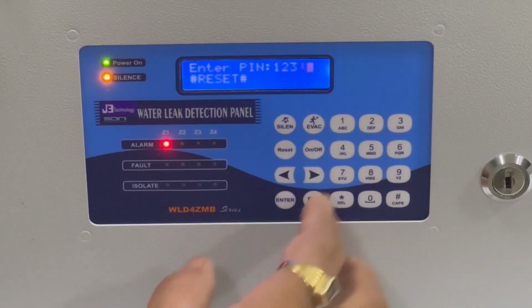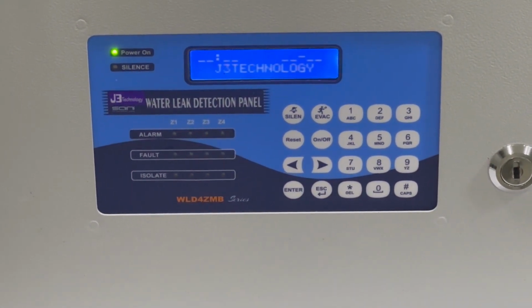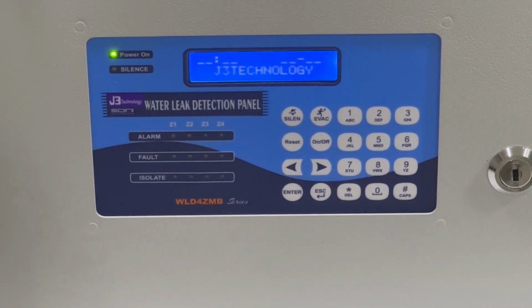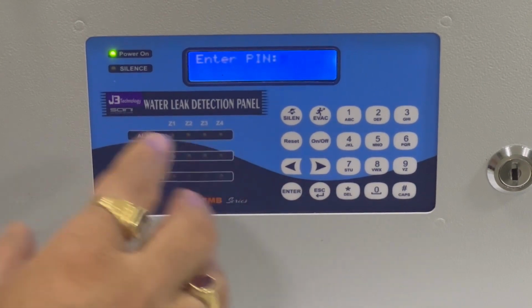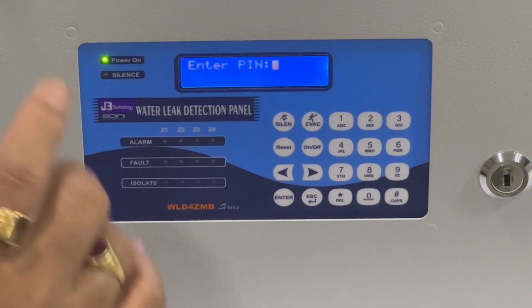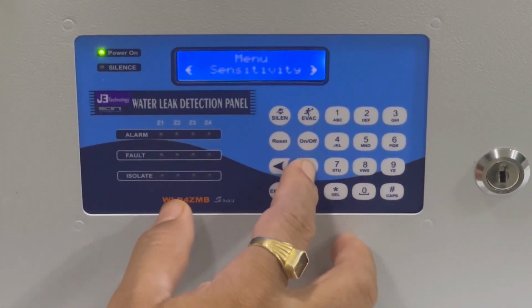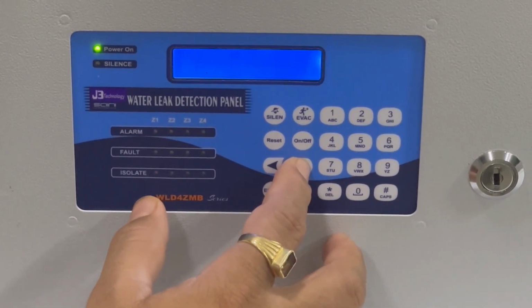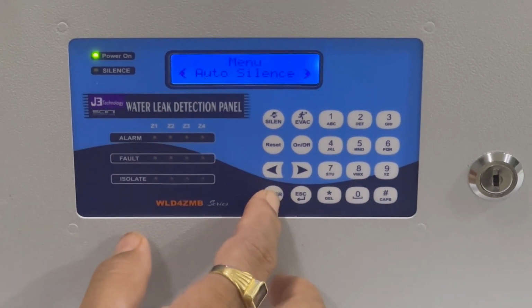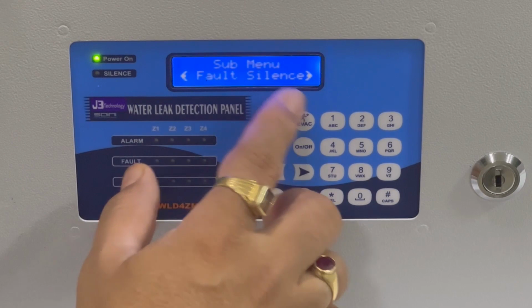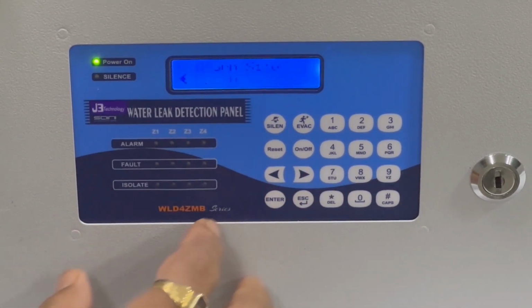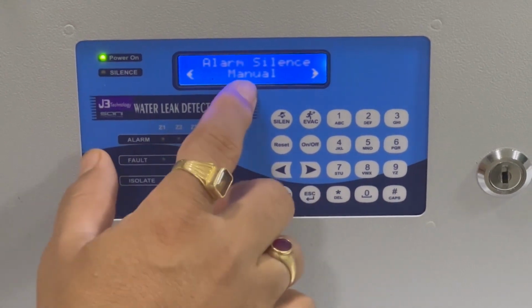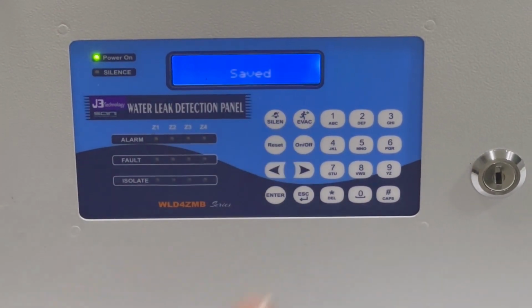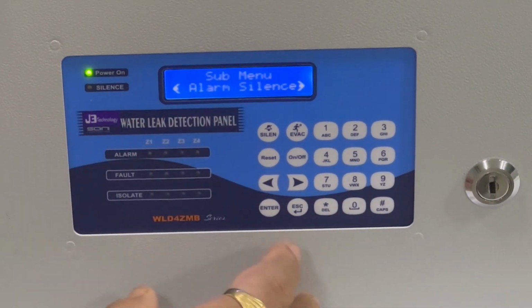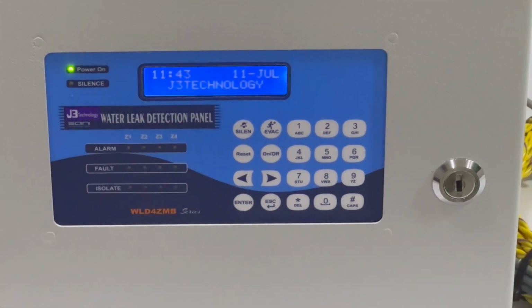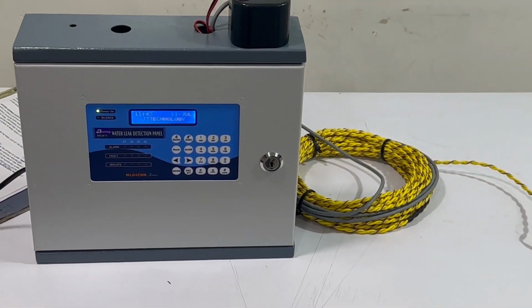1 2 3 4, the panel gets reset. Okay, now again I will keep the auto silence mode in manual mode. It will not get silenced unless I manually silence the panel. Now I am going to the auto silence mode. I enter this auto silence mode, and I go to alarm silence, enter. Now it is auto. I am going to manual. I press enter, it gets saved. Okay. Now I am generating the alarm, but it will not get silenced by itself unless I silence it manually.